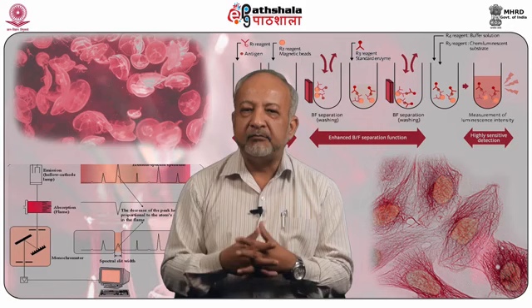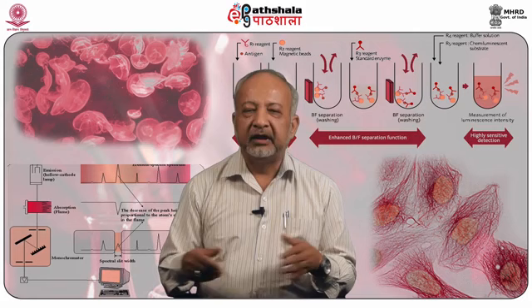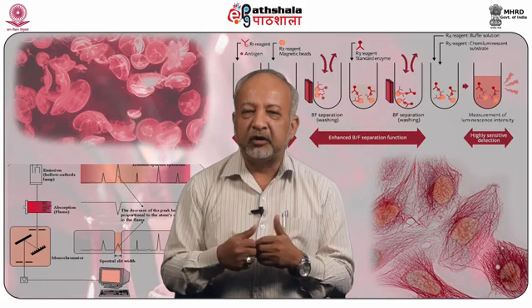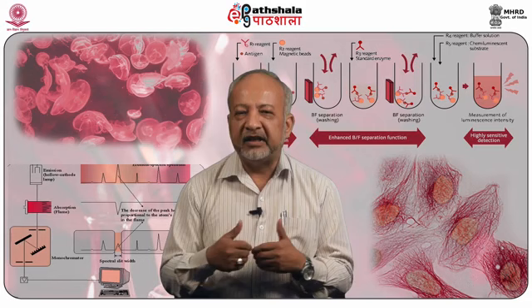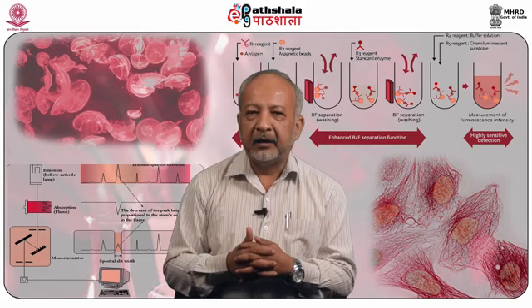For volatile compounds, gas chromatography is generally used as the inlet device, and GC-MS is available. For polar, non-volatile compounds we use liquid chromatography or HPLC coupled to a mass spectrometer, so LC becomes the inlet device for such compounds. A modern mass spectrometer normally has more than one inlet device; even capillary electrophoresis is coupled to a mass spectrometer.